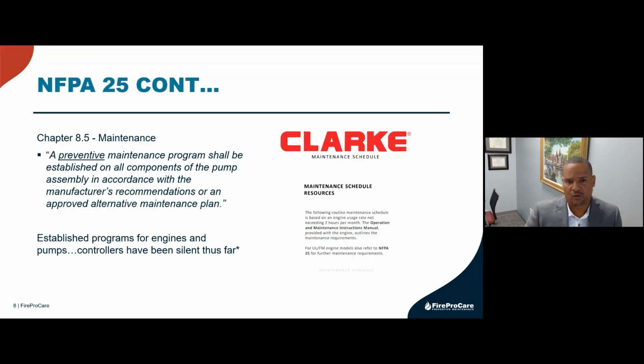Same philosophy goes with the engines, and it should go as well with the pump and the controller, which are the major parts of the fire protection system. It hasn't been done on controllers thus far. There may be some plans that local guys have put in place, but we want to make sure we can change that and have everyone utilizing the manufacturer's recommendations to ensure the best system possible in those situations.